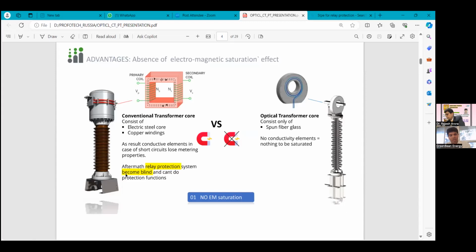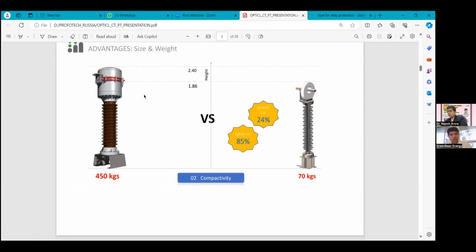From this conventional CT, the optical transformer core is made of only spun fiberglass, and there is no conductive element and nothing to be saturated. Advantage in size and weight wise. The conventional CT is 450 kg, in comparison the optical CT is only 70 kg. So weight wise it is lighter by 85% and smaller by 24%.